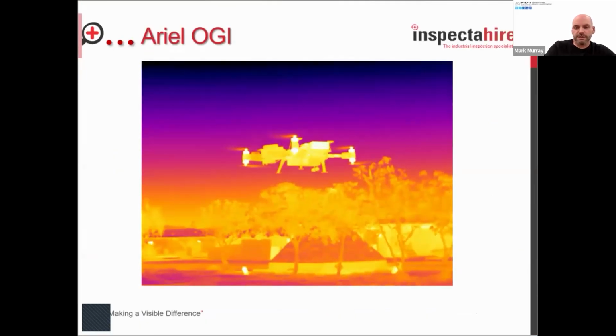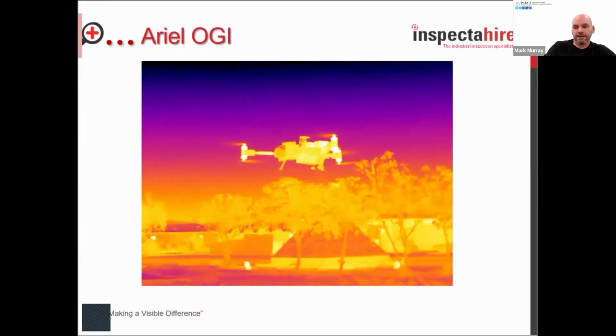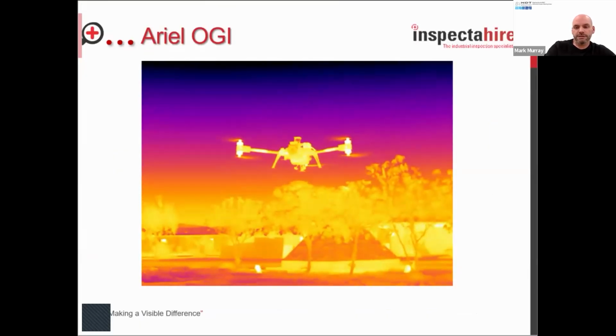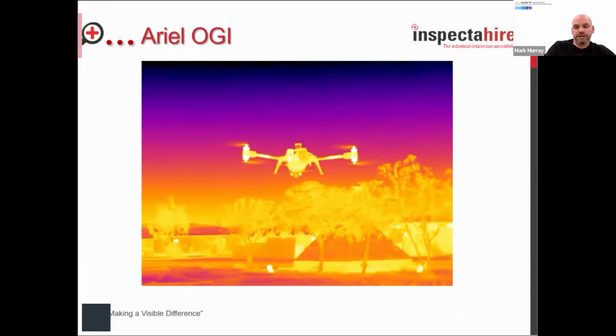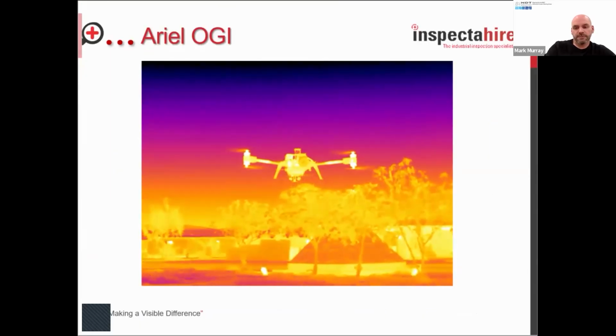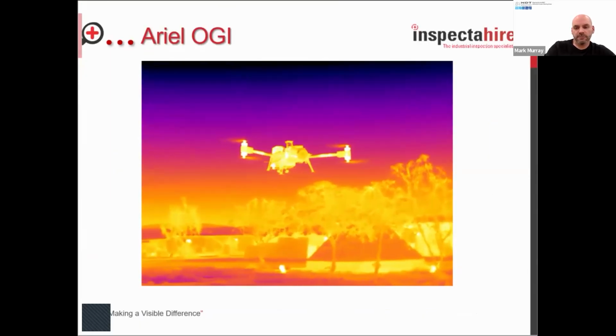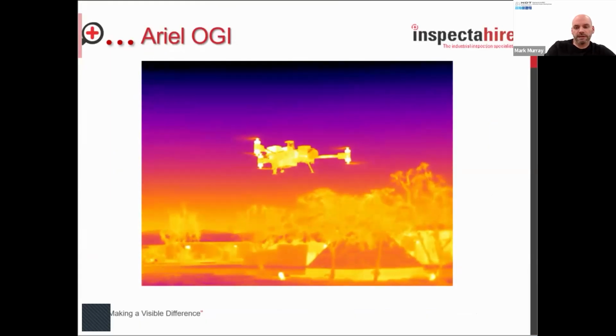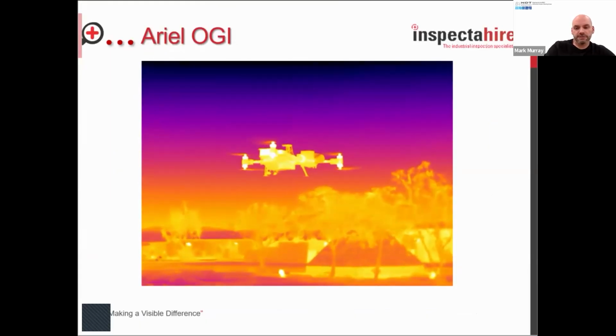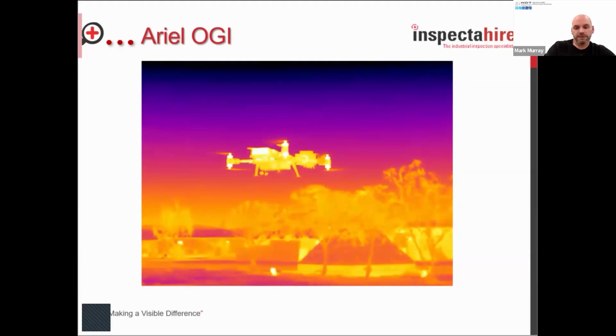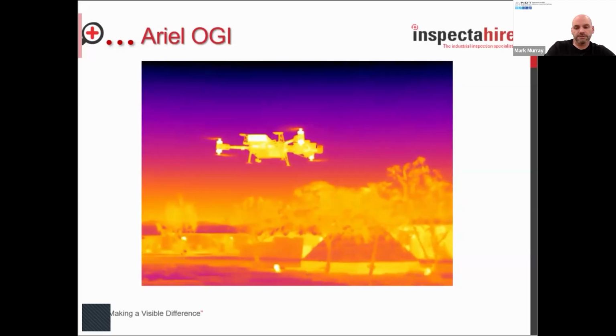The unit's mounted with a GF300A camera. In this video, we're using a T650 to check the temperature of the motors as the ambient temperature was nearing 40 degrees. This was out in Abu Dhabi. We were worried that they might be overheating during the survey, so we were just testing them prior to doing it.